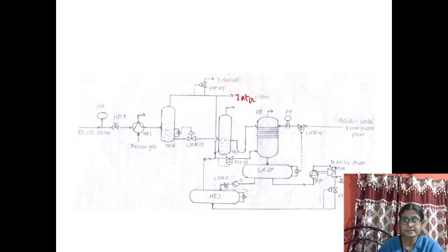So again this steam line is used and sent through the PIC 36 to the deaerator. If the upper level exceeds, then the steam quality will be affected by the water, and if it goes below the lower level, then a dry run may occur.